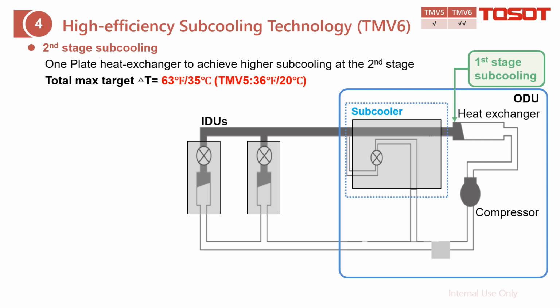Subcooling technology. For this one, which is only in cooling mode, the system will control the subcooler from the outdoor unit to the indoor unit. And here is the outdoor unit in this frame, and it just connects with two indoor units. So in cooling mode, the outlet of the outdoor heat exchanger has already become liquid, which is the first stage of subcooling, and then we send this through the subcooler. Actually, it is a plate heat exchanger, and then we send this liquid to the indoor unit.